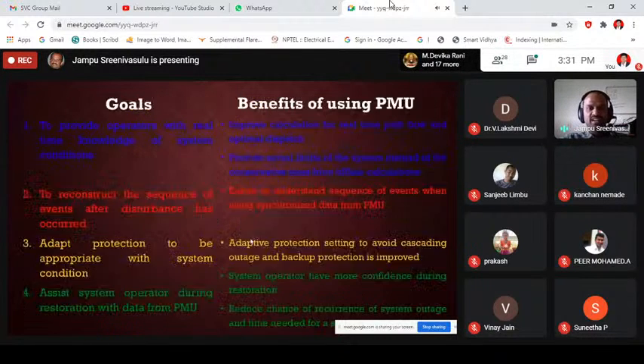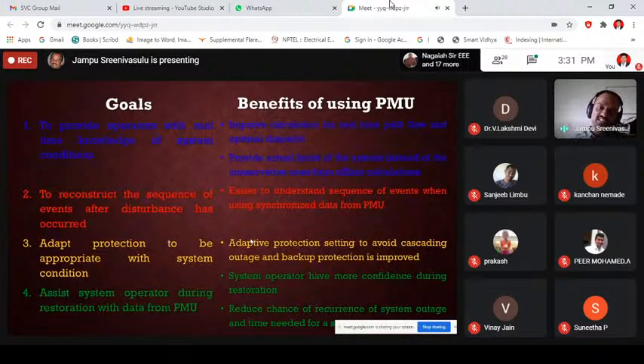And next, adaptive protection. You are supposed to provide protection with the help of the wide area monitoring system, which makes it easier to understand the sequence of events when using synchronized data from phasor measurement units. And adaptive protection settings avoid cascading outages, and backup protection is improved.